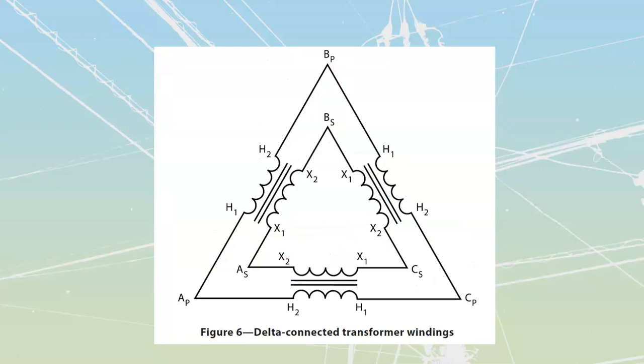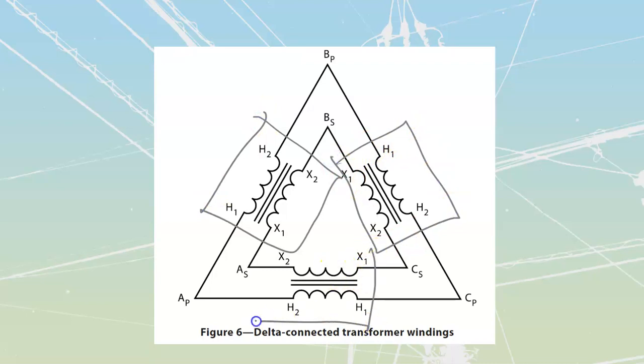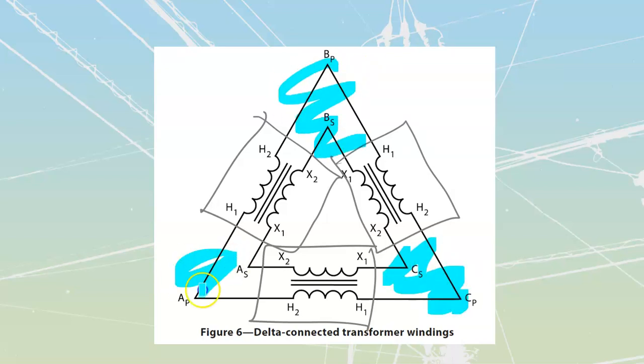The other connection we have is my delta-to-delta. Looking at these individual sets, the way they're drawn right now is just a triangle superimposed over another triangle. I could look at each of these as being either an individual leg on a three-phase transformer core, or as three individual transformers connected into a bank, with all of these connections made externally. Either one is perfectly acceptable.